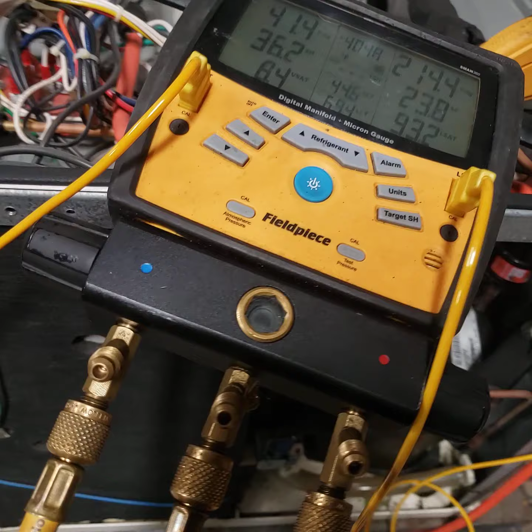So we're gonna wait, and we're gonna watch another harvest together. Okay, so remember, this is low. Okay, I have a different color. Usually it should be blue, but I put, it's messed up in here. So this is the low side. Usually goes to the blue, which is low, and this is the high side, which goes to here. Now the probe goes to the liquid line, which is here. I couldn't grab it; it's too small, so I had to grab it this way. And the other probe should go after the outlet of the evaporator, which is here.